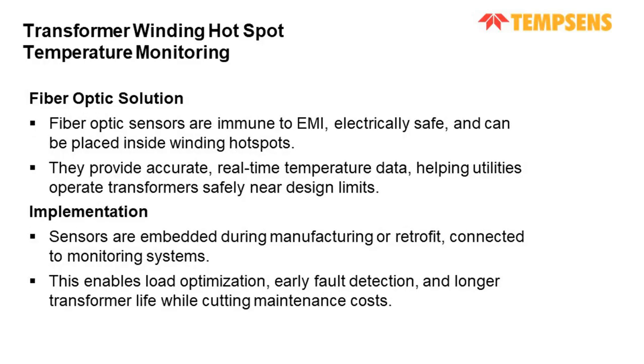What will be the solution? So we suggest a fiber optic solution. This is where fiber optic temperature sensors come in. Unlike conventional sensors, fiber optic sensors are immune to EMI and completely dielectrically safe because they don't have conductive parts. And this allows them to be embedded directly into the winding hotspot.